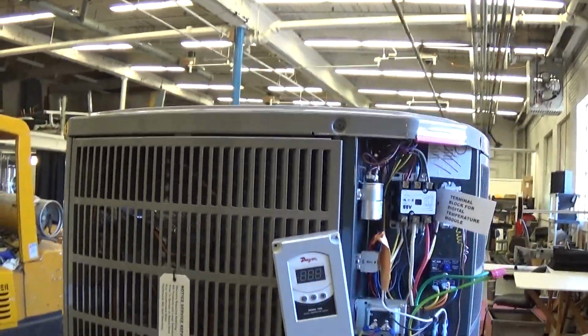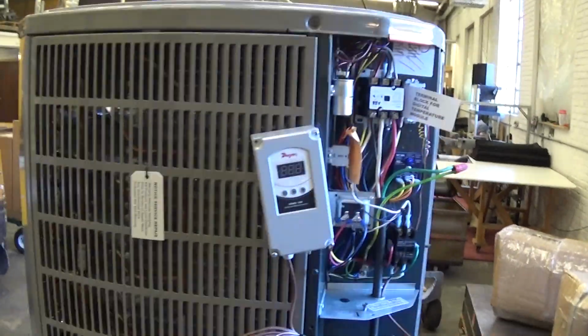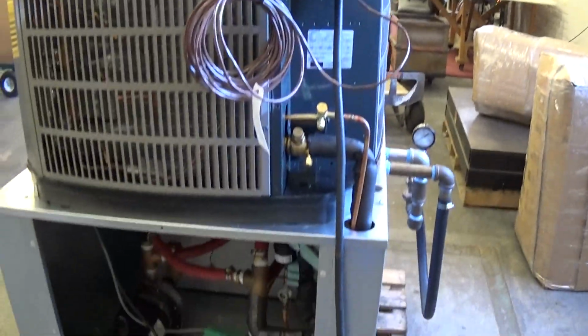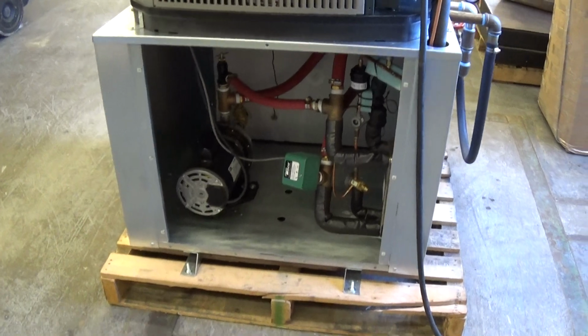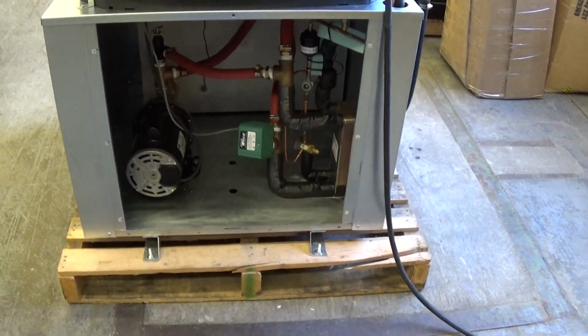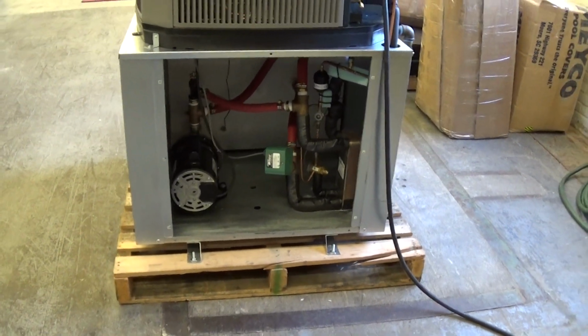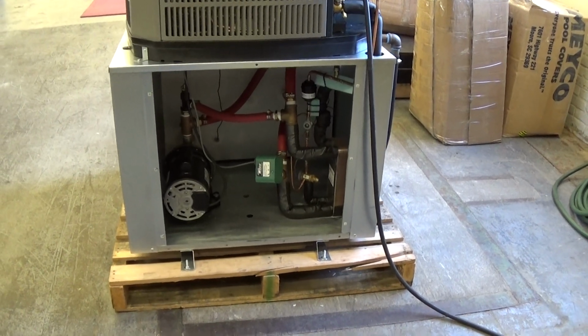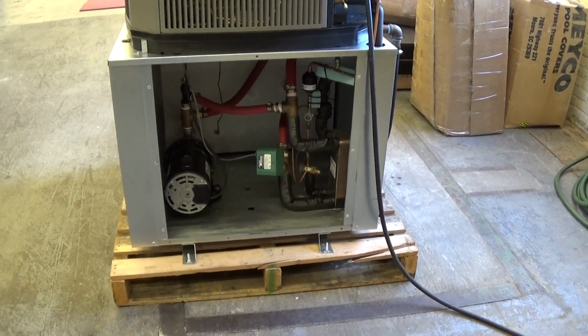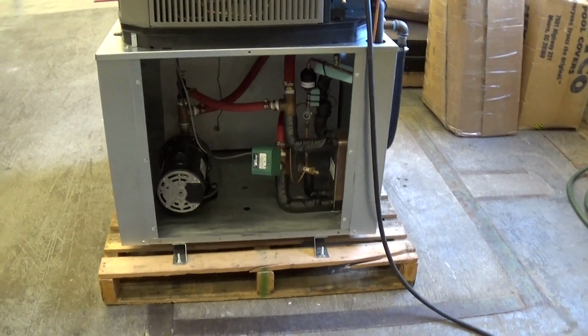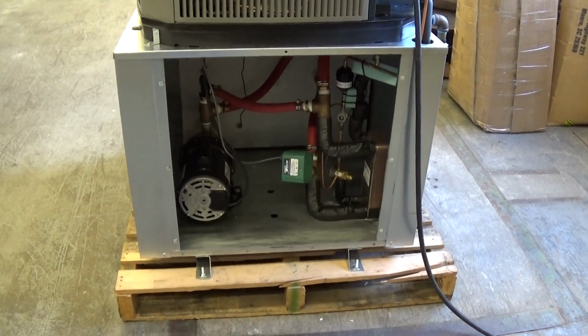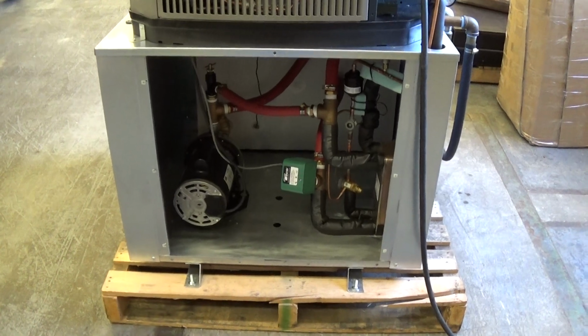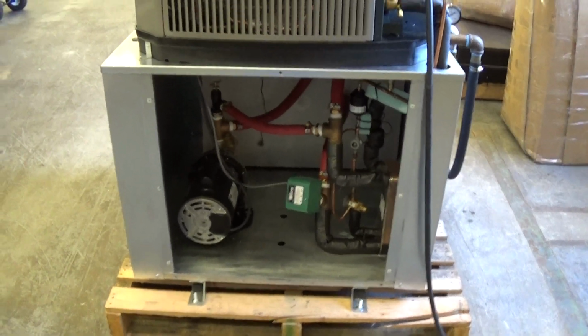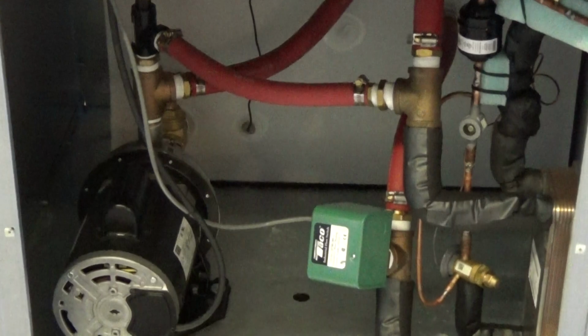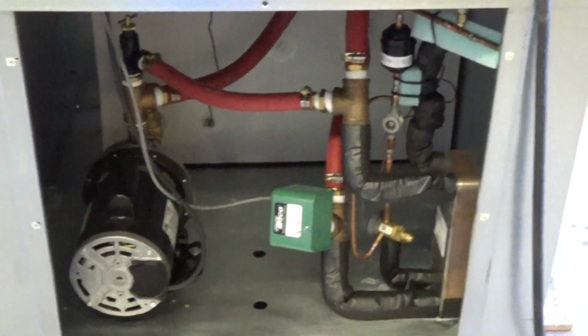The top section of the unit is the fan and condenser and compressor. The lower section is some of the refrigeration pipe, tank, and pump. Now in this case, this is going outdoors in a warmer environment, and we're going to run fairly warm process temperatures. So this unit, as opposed to one that we make this size for a colder glycol application, does not have insulation on the tank or the pump or the internal glycol lines.